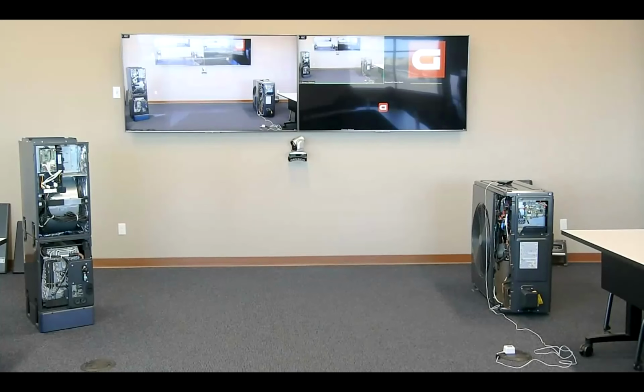Toby, I see your question there. It depends on where you're at, so drop me an email with your contact info, or drop it in the text here, and I'll reach out to you and discuss that in a little detail, so we make sure to get you the right info, because it depends on your area. For Washington specifically, we have found that Washington does not require the manufactured home approval rating. What they do require is that the system has an AHRI rating and that you document and verify airflow. You have to have that document on site for the inspector when they go to inspect it. They also have a checklist.